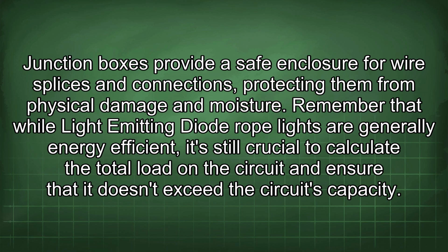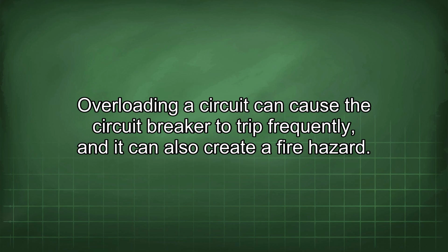Remember that while light-emitting diode rope lights are generally energy efficient, it's still crucial to calculate the total load on the circuit and ensure that it doesn't exceed the circuit's capacity. Overloading a circuit can cause the circuit breaker to trip frequently, and it can also create a fire hazard.